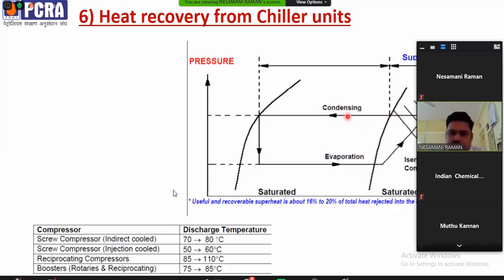What are the advantages? We'll see. These are examples of chiller compressors by type, showing how much the discharge temperatures will be. Reciprocating compressors will have the highest discharge temperature, and screw compressors will have a little less, around 80 degrees Celsius.